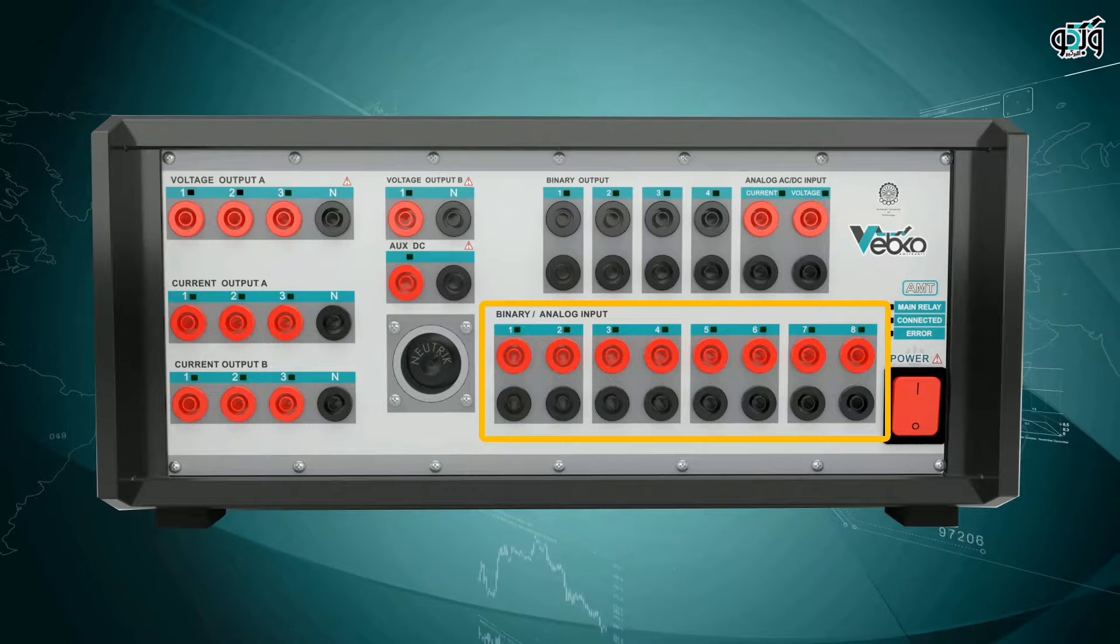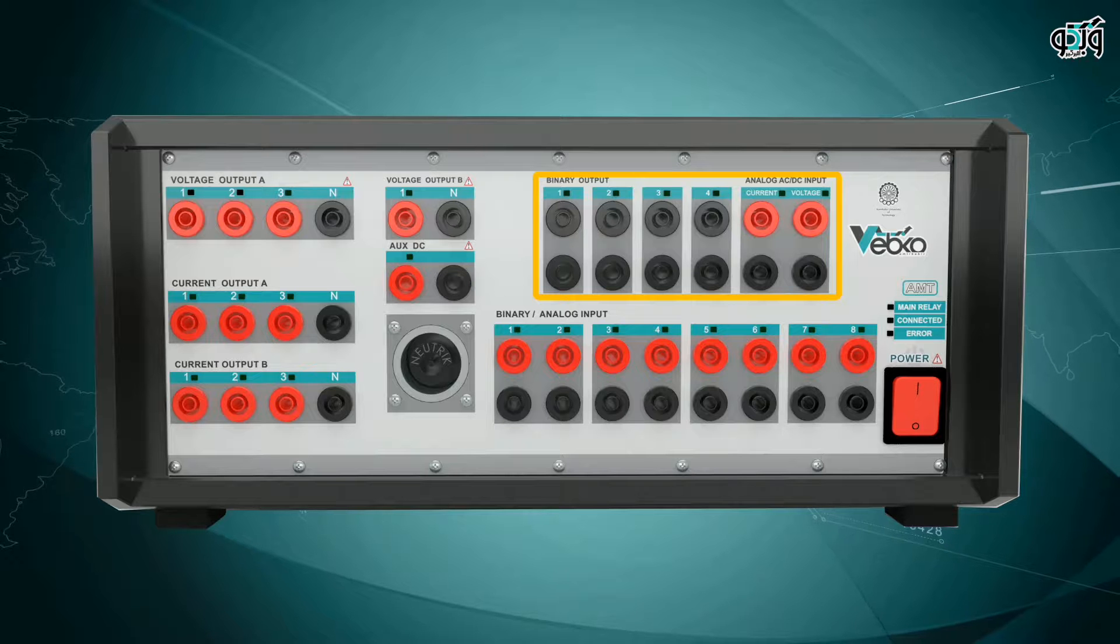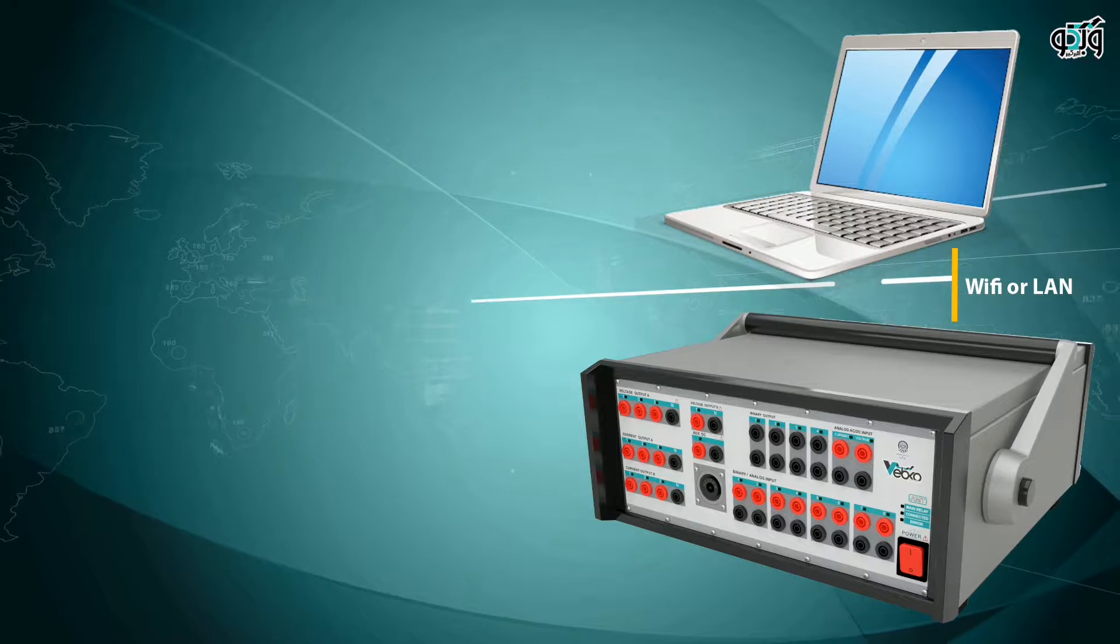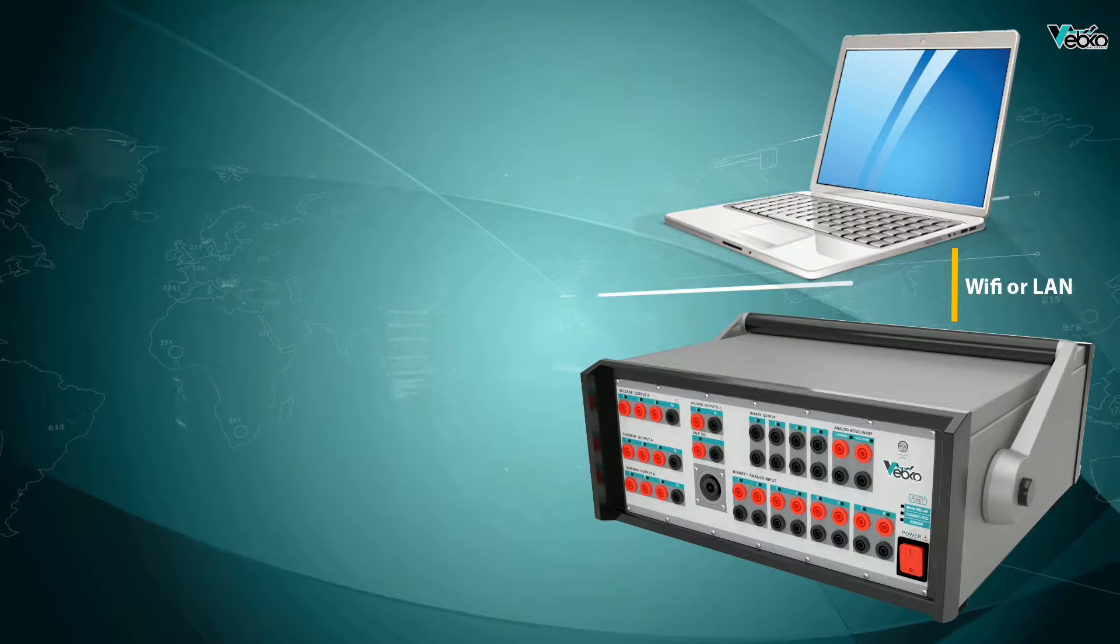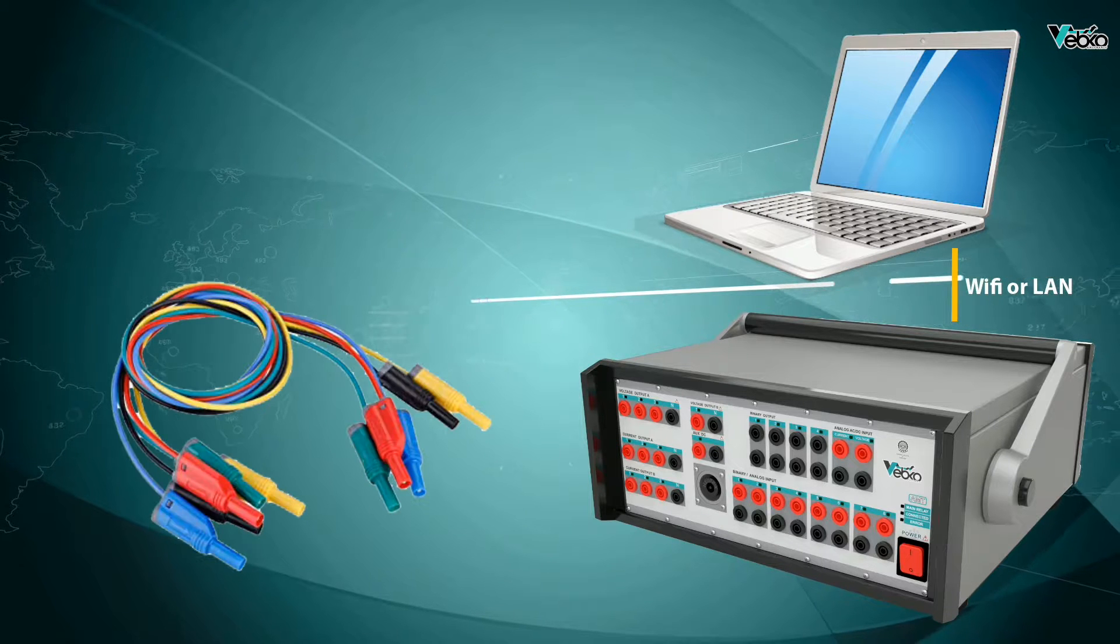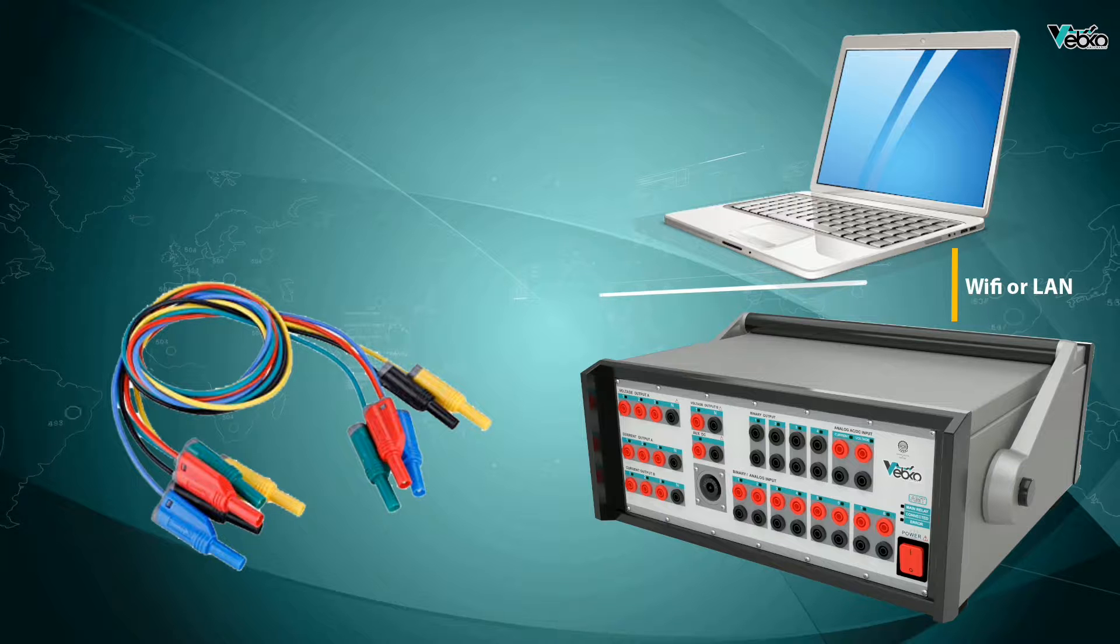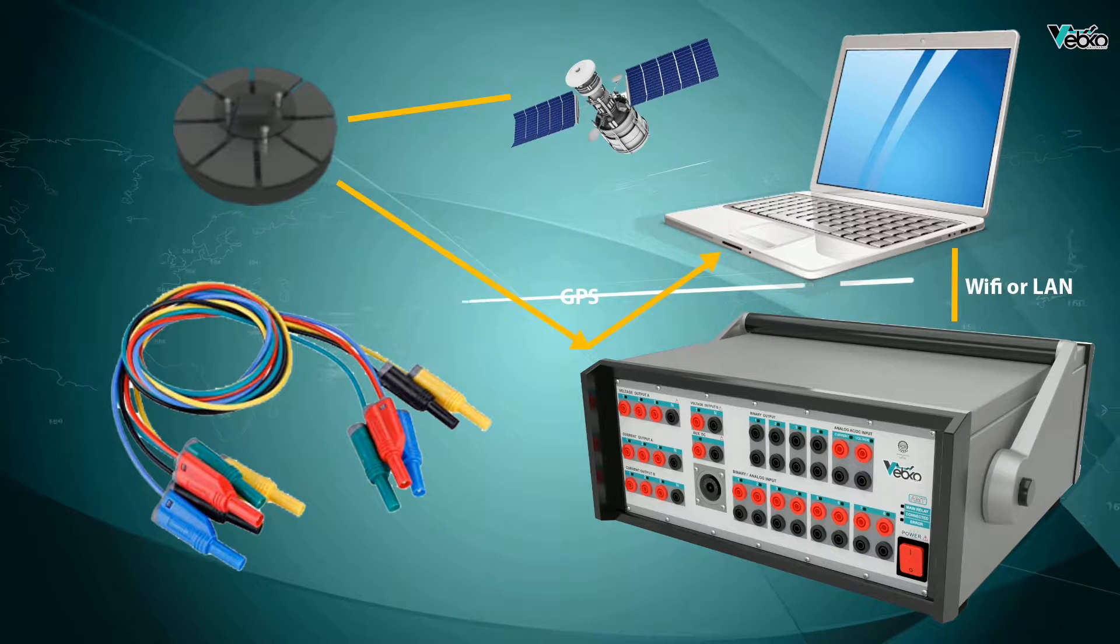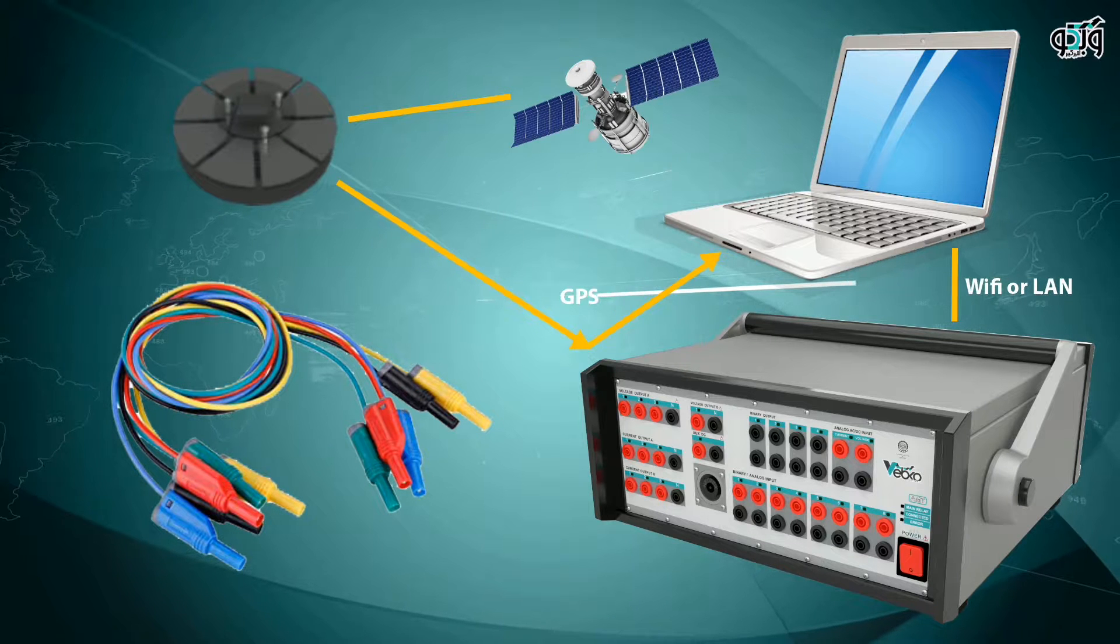Binary outputs can be used in cases such as circuit breaker status or simulation. In the next step, the test device voltage and current injection cables should be connected to the relay or test block to replace CT and PT for injecting the desired amounts. The GPS antenna is connected to the back of the device to use the GPS time as the base time.